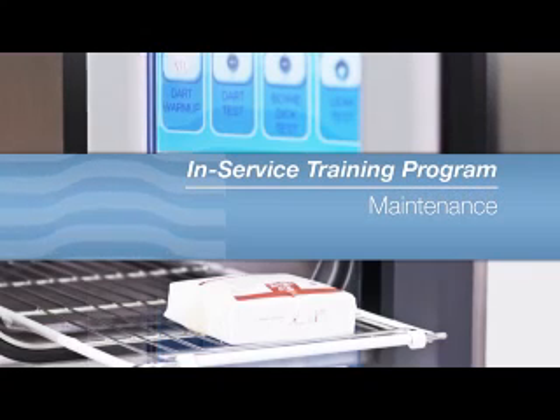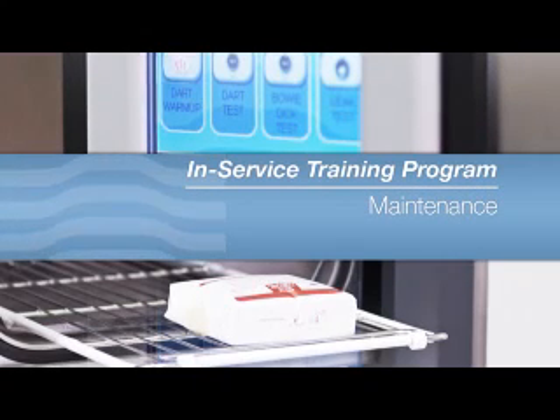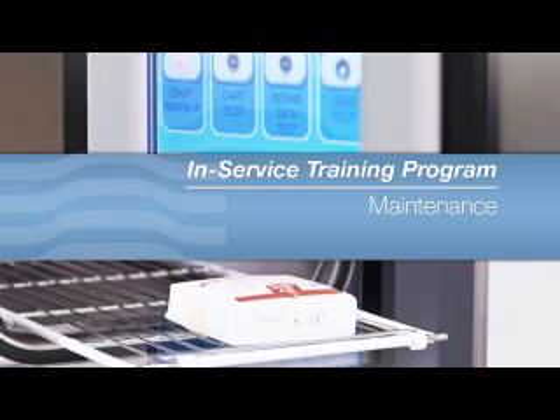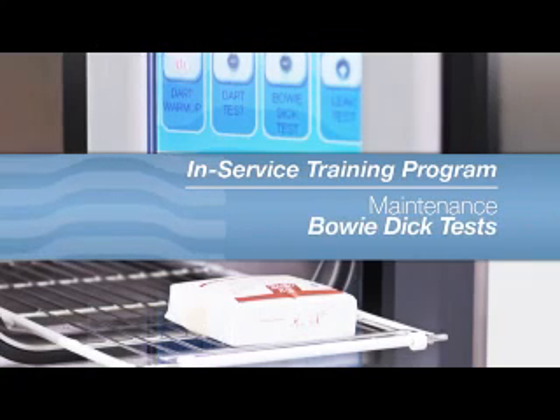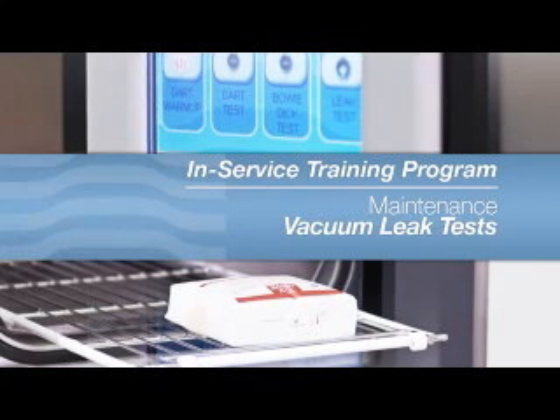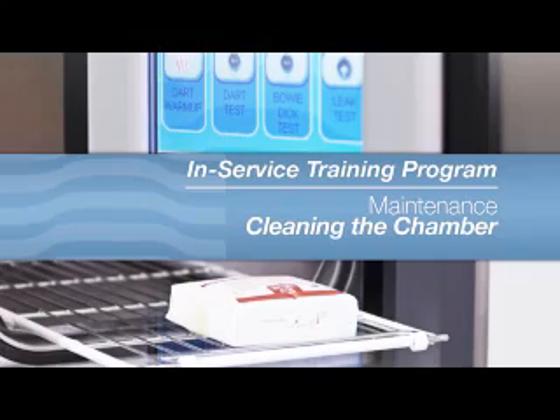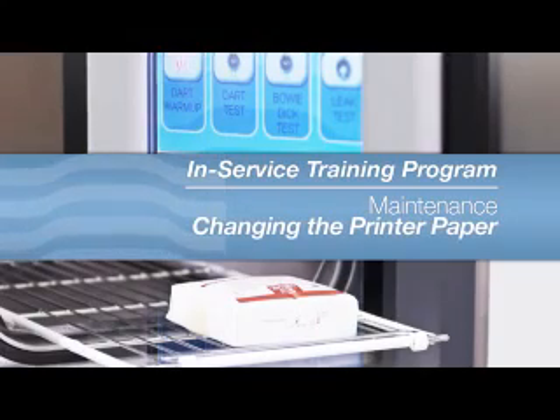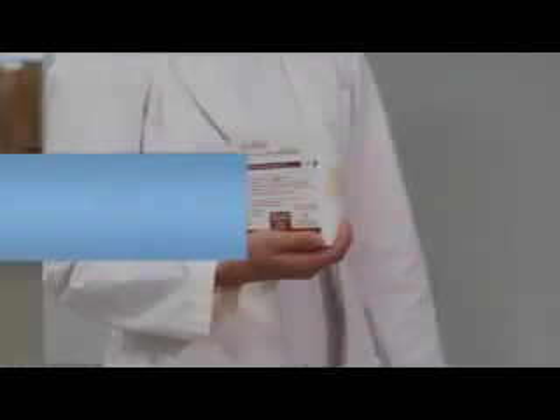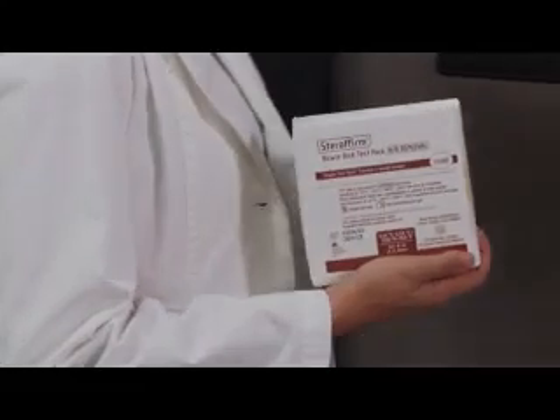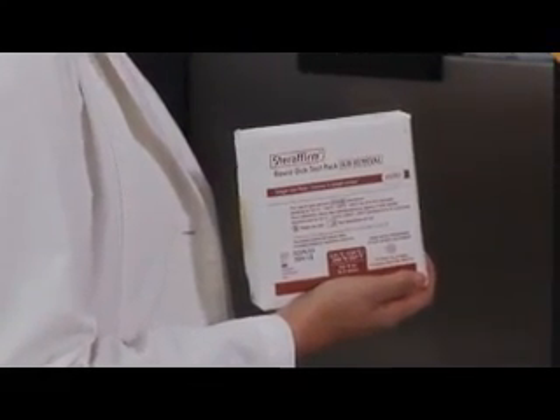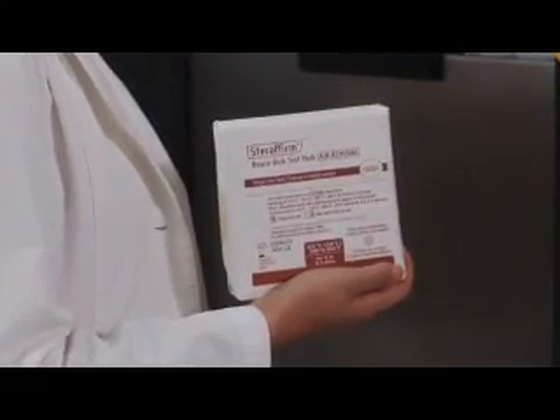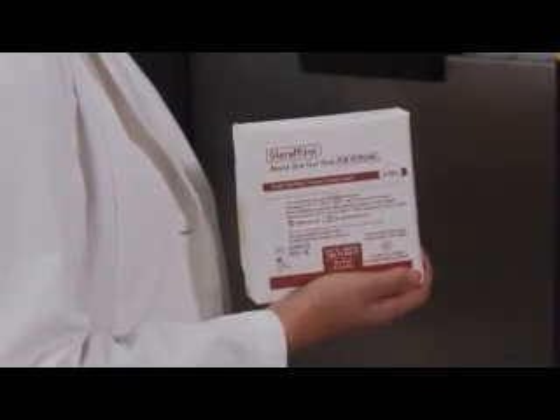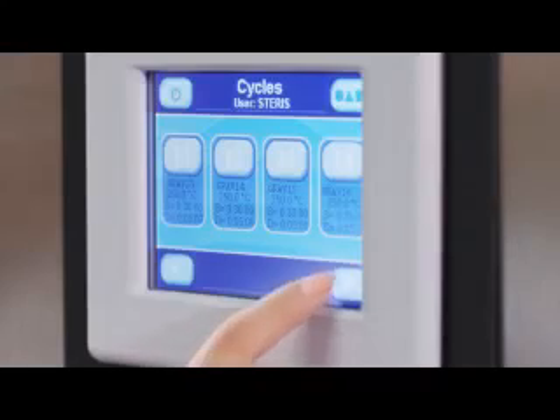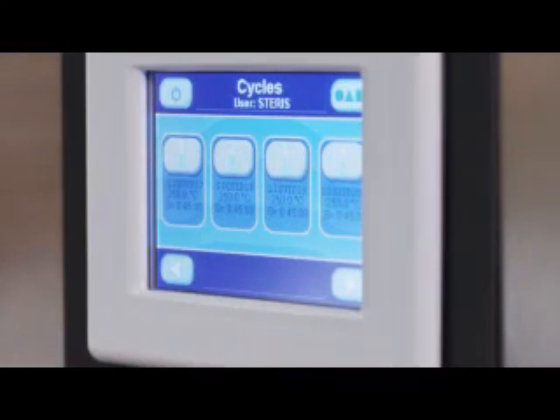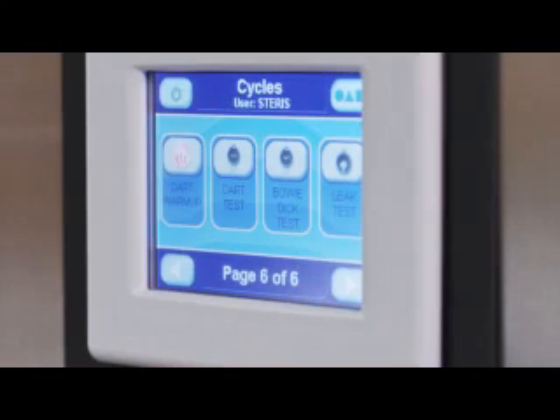There are a few easy maintenance considerations for the AMSCO Lab Series sterilizer. These include DART or Bowie Dick tests, vacuum leak tests, cleaning the chamber, changing the printer paper, and flushing the generator. The DART test and the Bowie Dick test are means to ensure proper air removal from the chamber and load items. These are not tests for adequate sterilization. These test cycles are found in the cycle menu on the last set of screens.